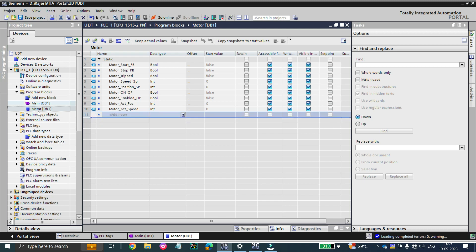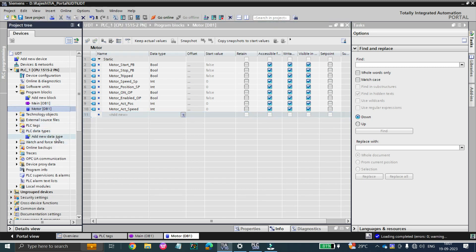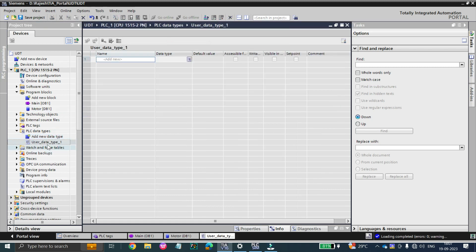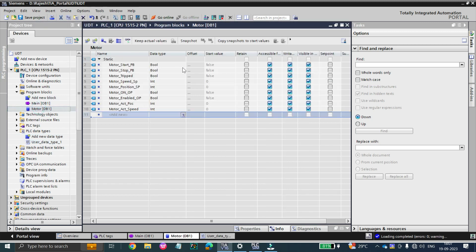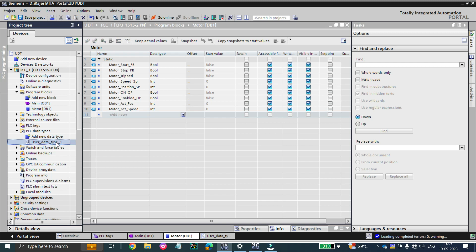To avoid this problem, what we will do is use PLC data types. By expanding PLC data types, there will be an option called 'Add new data type.' Normally you know data types as boolean, integer, and so on — but this data type means it is your own data type, a user-defined data type that you are creating in the PLC.